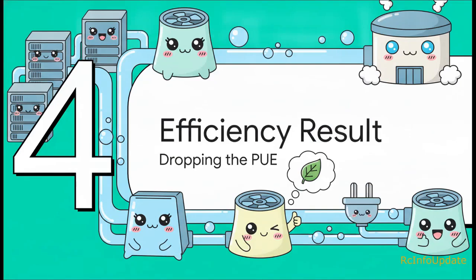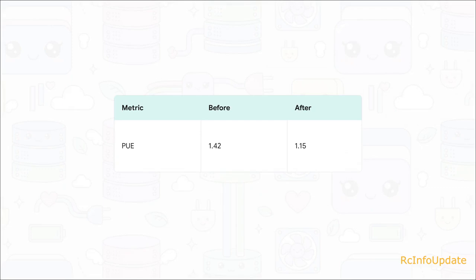Which brings us to part four, the efficiency result, dropping the PUE. Because these liquid cooling moves actually work, and we've got the hard numbers to prove it. Power usage effectiveness, or PUE, measures wasted cooling energy. Lower is definitely better here. By using liquid cooling, we crush the PUE from 1.42 down to a sleek 1.15. That is just massive, massive energy saved.